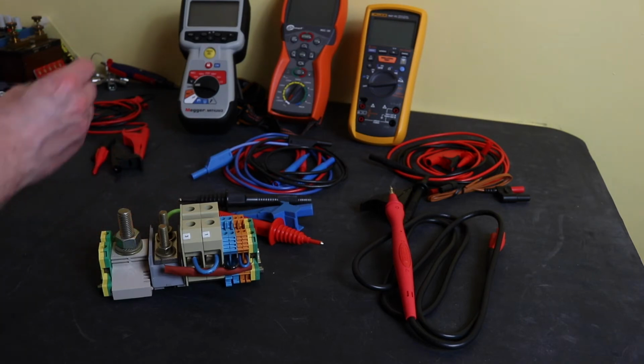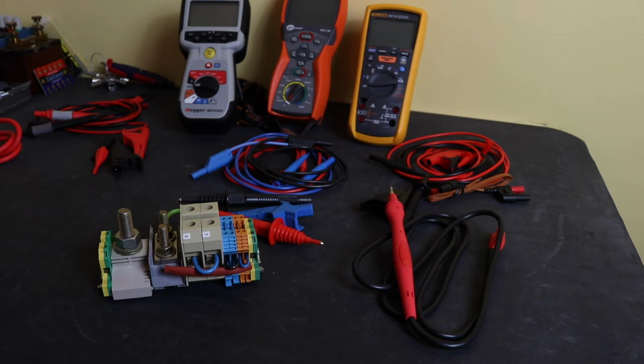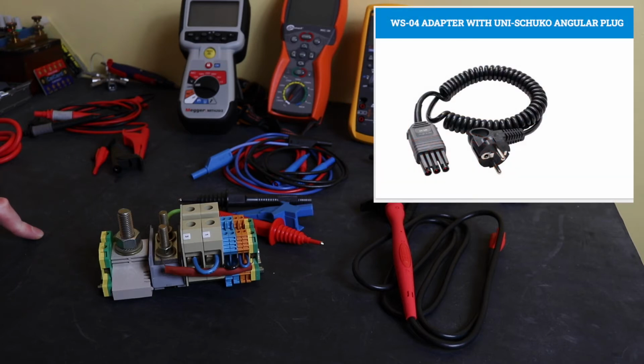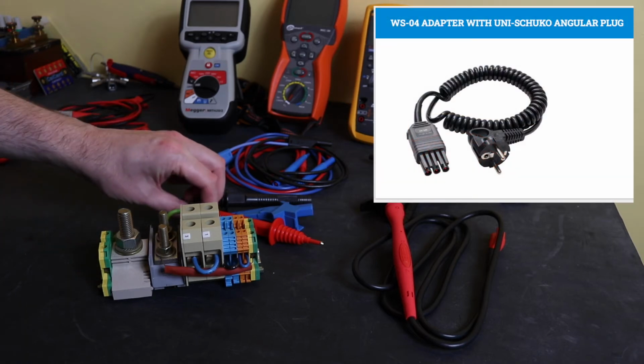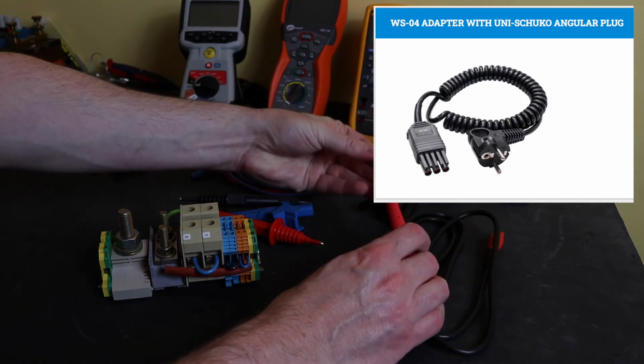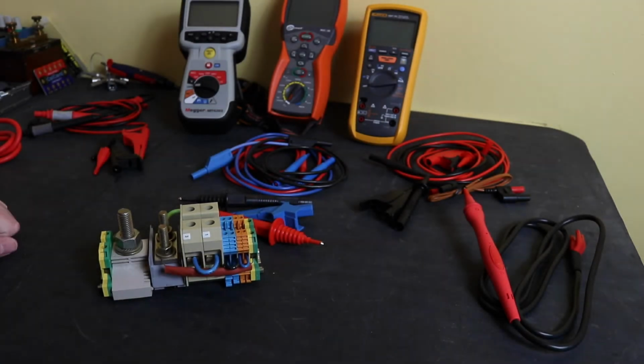As I said, the Sonel doesn't come with a remote probe. I don't believe there is a facility for the instrument. It does have what's called a WS04 adapter that plugs into the top of the instrument and allows automated insulation testing to be carried out on a single phase live, neutral and earth system. I don't actually have that adapter to demonstrate. It's only available with a Schuko style connector on it, which isn't compatible with my country. Neither the Megger nor the Fluke offer any form of automated testing in that manner.